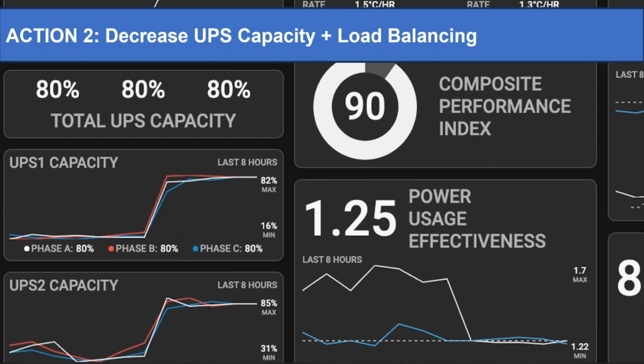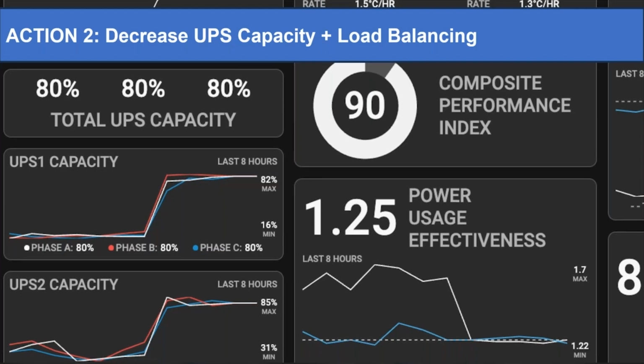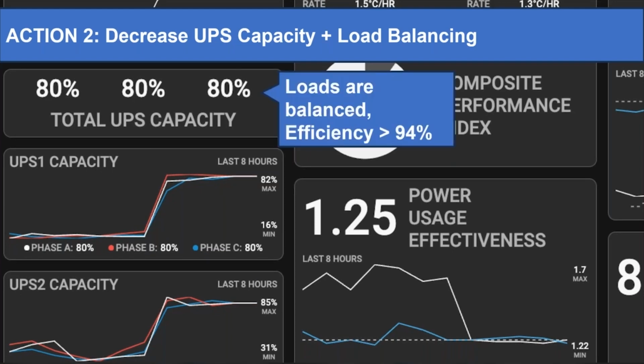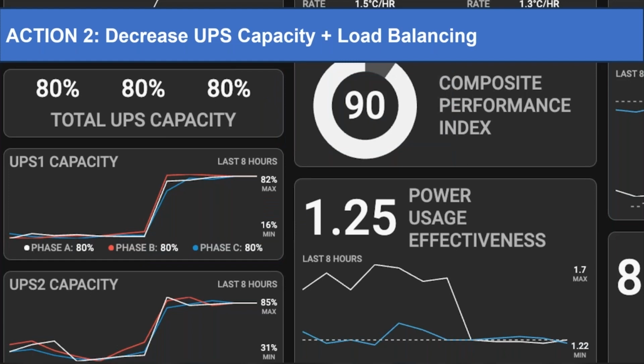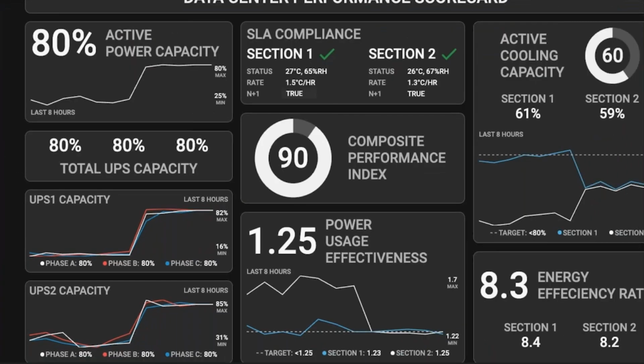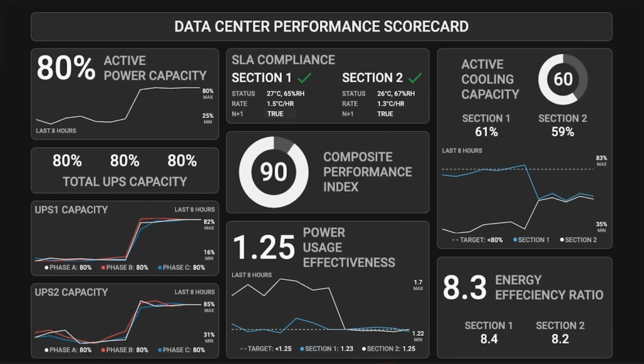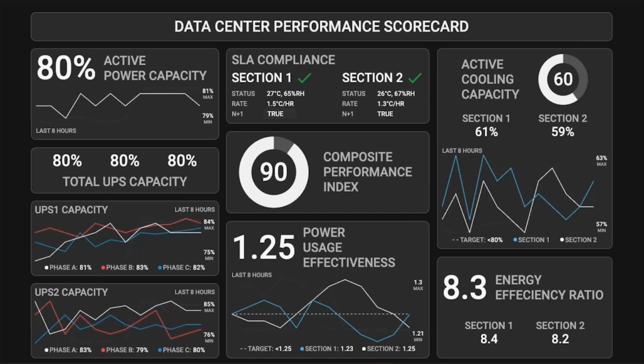We detached from a modular UPS segment and we balanced the load. And what's interesting right now is that our efficiency went up from 87 to 94%. So we also gained quite some on the UPS part, and now our PUE is below 1.3, it's even 1.25. Do you remember in the beginning that the operation manager said, well, I did everything I could and there is nothing I can do? Well, actually he was right, because he had no idea. He didn't have the tools. But if you have an integrated DCIM system and you put everything in, in this case a balanced scorecard, you have so much more knowledge and tools to help you.